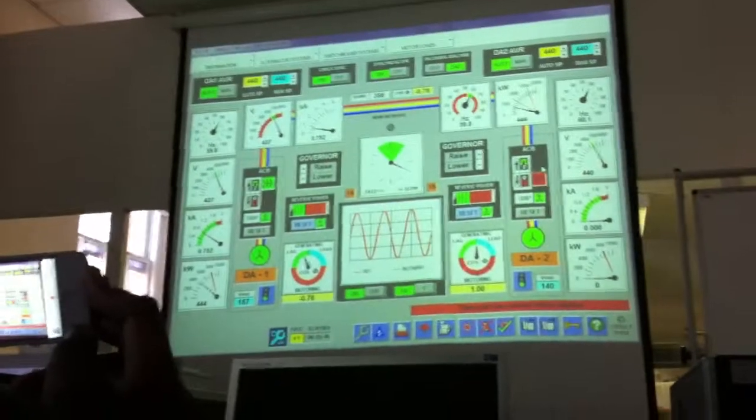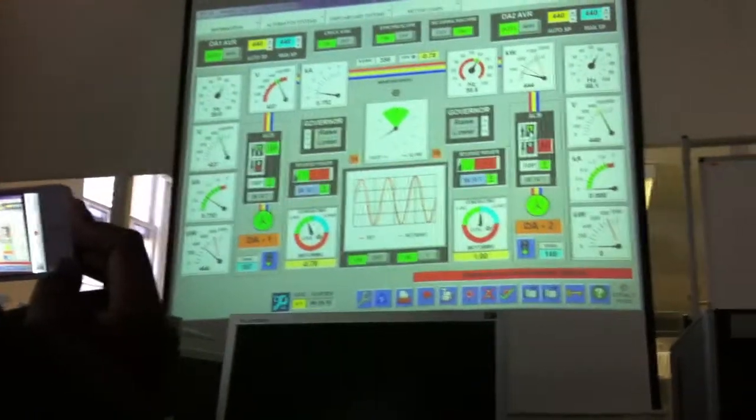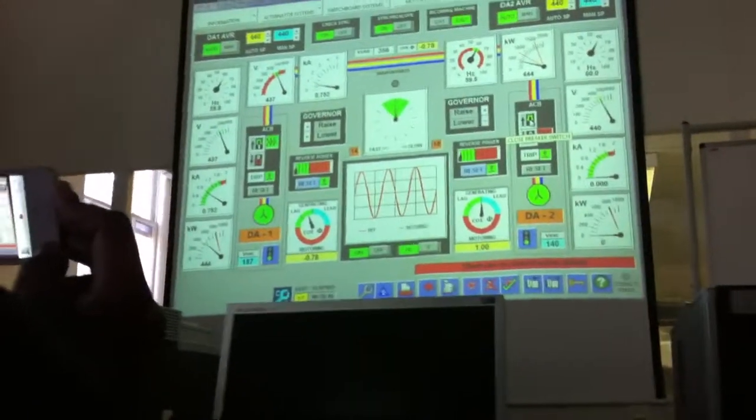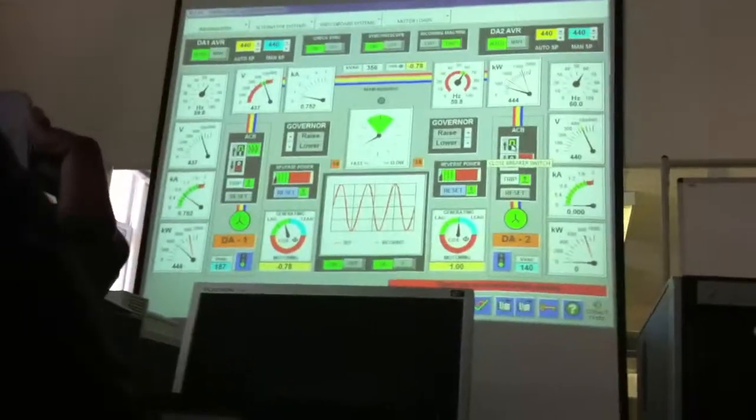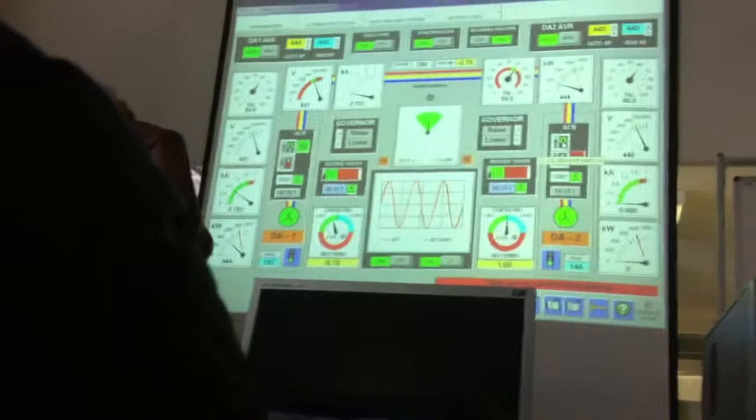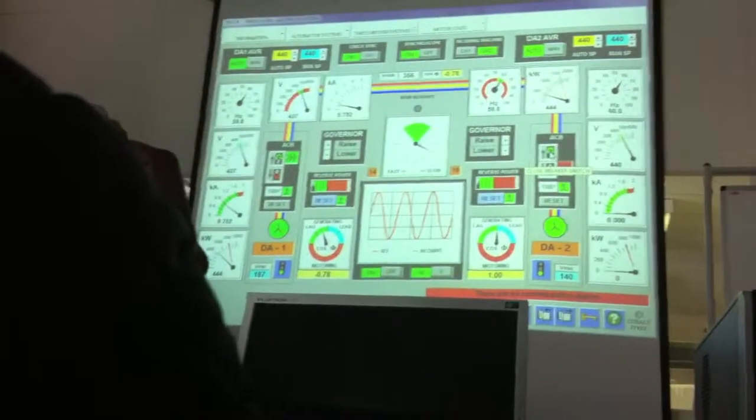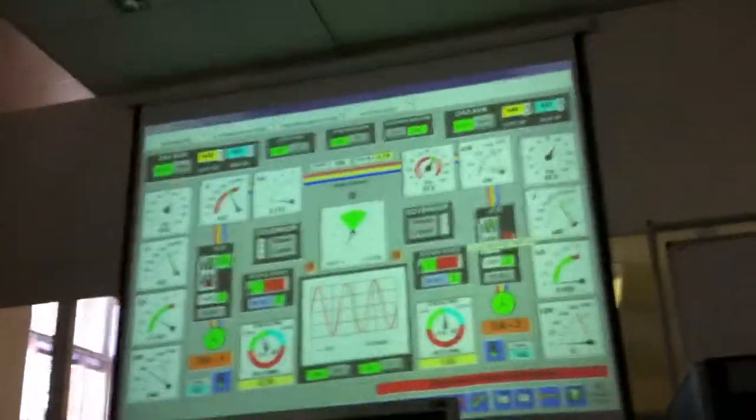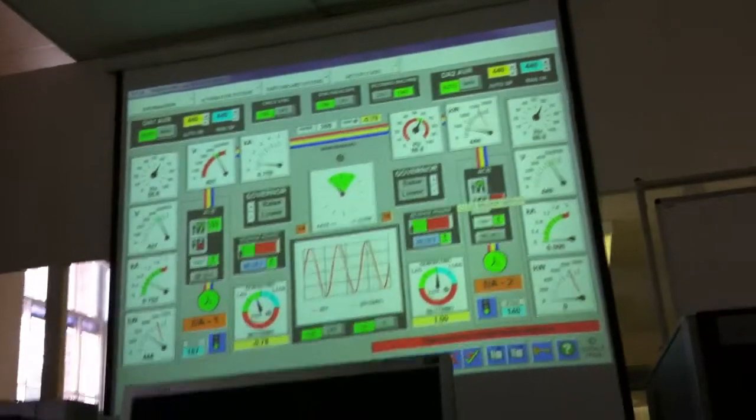Now the next key thing, reset, get ready over the main breaker to close it. I do not want to hear people talking of putting the breaker on. We don't use that terminology. We close a breaker or we open a breaker. We don't put them on and off.